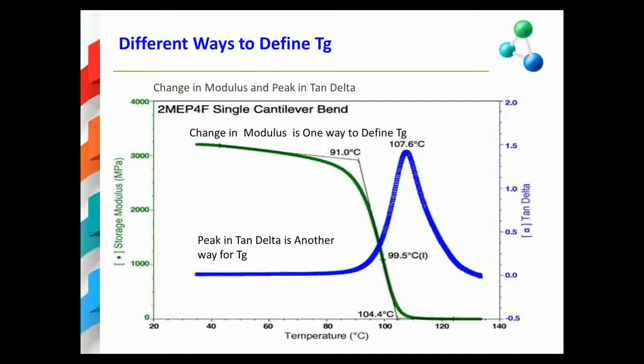A quantitative and reproducible value for the temperature at which E prime begins to decrease can definitely be determined from the analysis shown on this slide. The analysis involves fitting E prime data to three lines before the transition, during the transition, and after the transition, and determining the intersection points of the various lines.